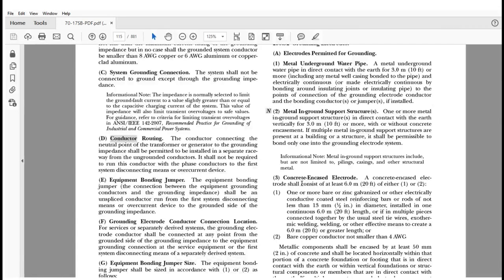Basically what it's saying, and remember, we're dealing with something that's potentially different than a concrete encased electrode application. What is a metal in-ground supporting structure? One or more metal in-ground supporting structures in direct contact with the earth vertically for 10 feet or more, with or without concrete encasement. So the title of metal frames of buildings, grounding electrodes, that was here before, has been renamed to metal in-ground support structures. That is what changed here.